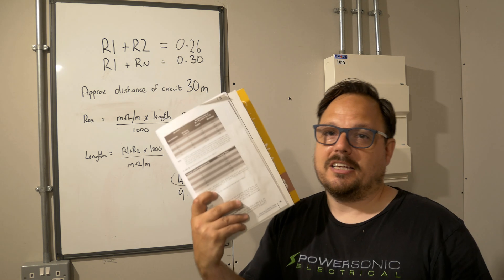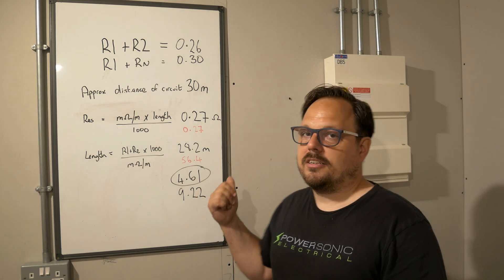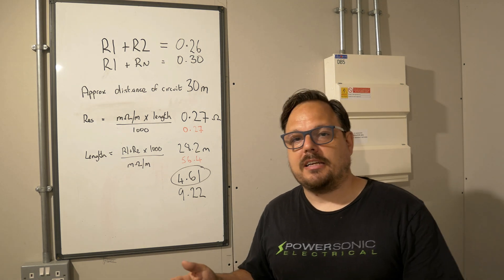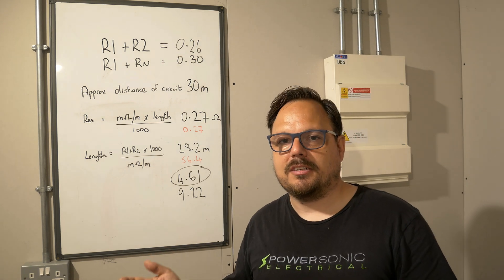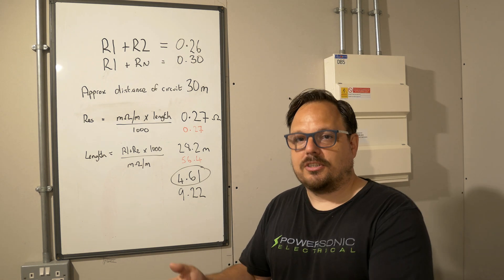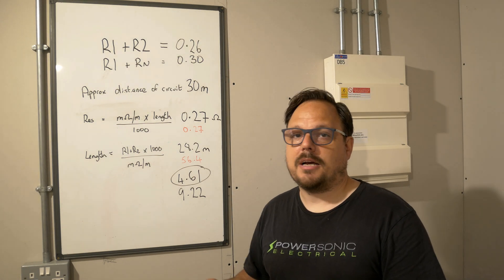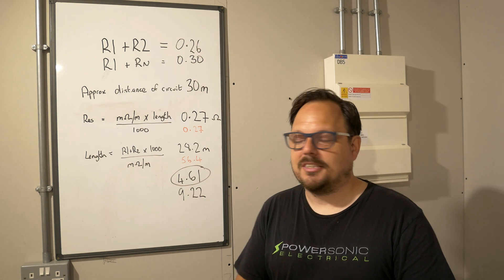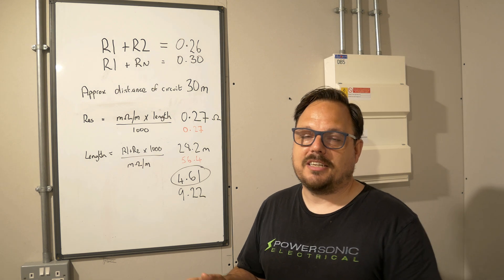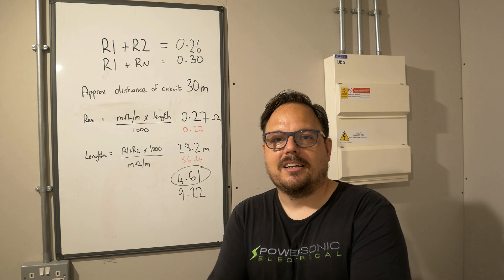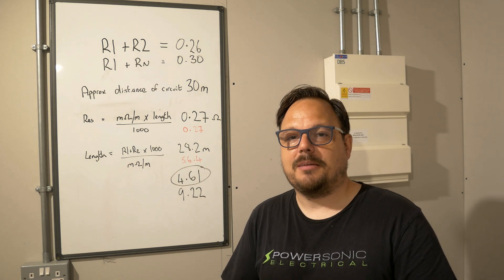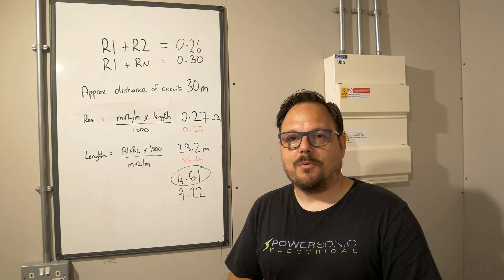The tables are in the On-Site Guide and also in Guidance Note 3 — page 182, spilling over to the next page for larger size conductors. You can play around with the maths and double check that the values of resistance you're measuring play out alongside what the calculations show they should be. If you've got a design and drawing on a large and more complex installation, that's going to be really helpful for approximating circuit lengths to compare to your measured test values and see how parallel paths might be affecting your R1 R2 measurements. If you've got any questions around continuity testing of your R1 R2s and the differences between the little and big letter designations, please drop them in the comments. Thank you for watching and I'll see you on the next one.